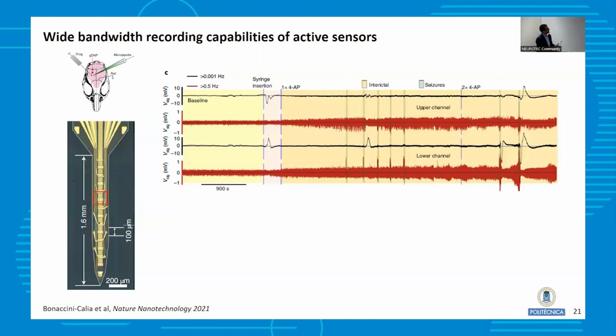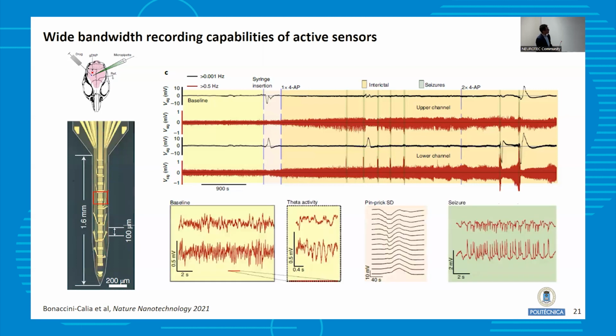The interesting thing here, for those who are experts in the field, is that you can of course record over hours without any drift in the recordings. And this is very, very important. Typically, when you do recordings over hours with passive electrodes, if you're measuring low frequency, you need to continuously reset the amplifier because of drifts. But you can record for hours without any drift. You can record baselines precisely, standard activity like theta bands, and seizure-type activity with very high precision.